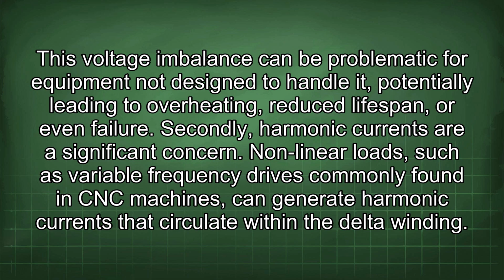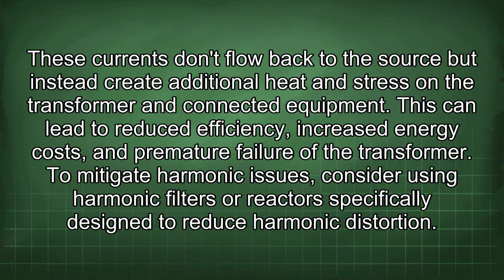Nonlinear loads, such as variable frequency drives commonly found in CNC machines, can generate harmonic currents that circulate within the delta winding. These currents don't flow back to the source, but instead create additional heat and stress on the transformer and connected equipment. This can lead to reduced efficiency, increased energy costs, and premature failure of the transformer. To mitigate harmonic issues, consider using harmonic filters or reactors specifically designed to reduce harmonic distortion.